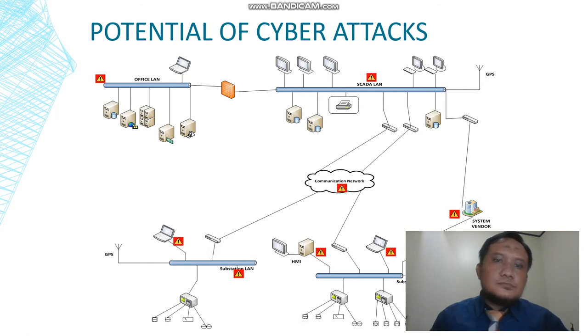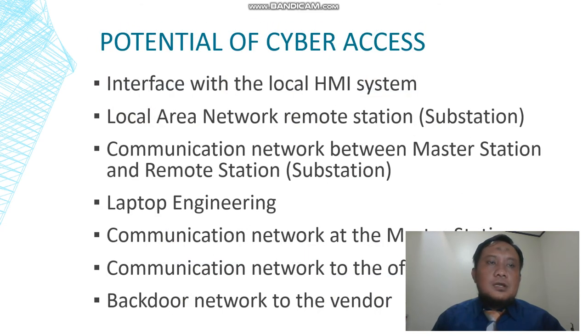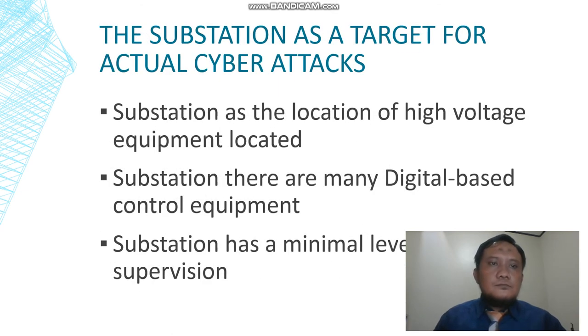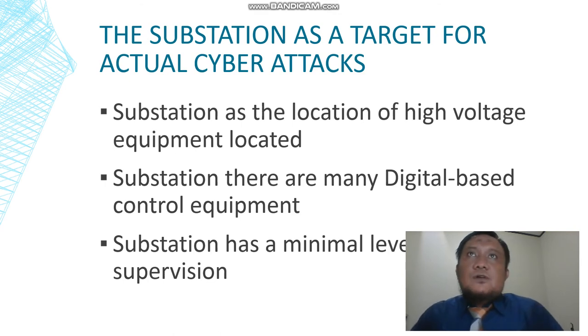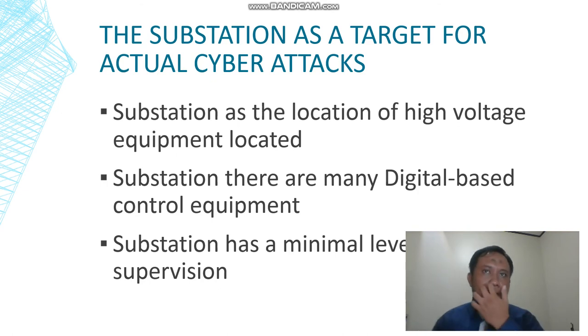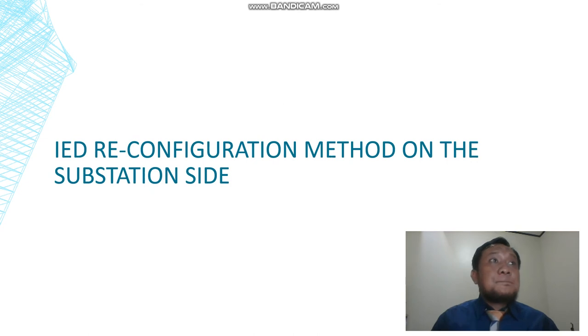Potential of cyber attack. In general, every attack on the SCADA system is in the data communication part. Potential cyber access points include the local HMI system, the local area network at the remote station, the communication network between the master station and remote station or substation, the engineering laptop, the communication network at the master station, the communication network to the office, and the backdoor network to the vendor. Substations are a target for actual cyber attack. The substation is the location where high voltage equipment is located. In the substation there is a lot of digital-based control equipment, and the substation has a minimal level of supervision.